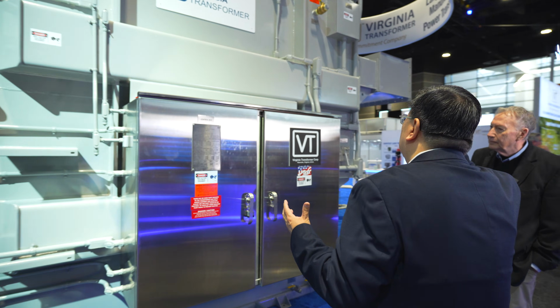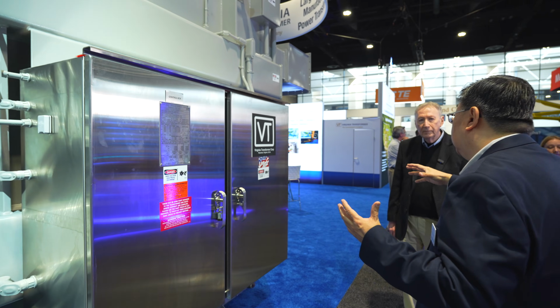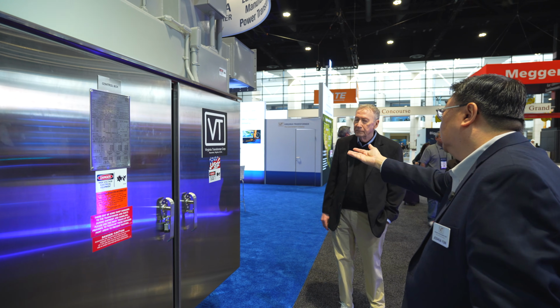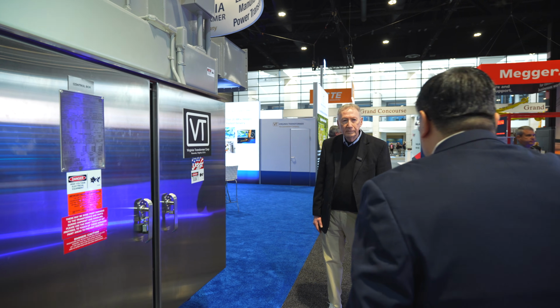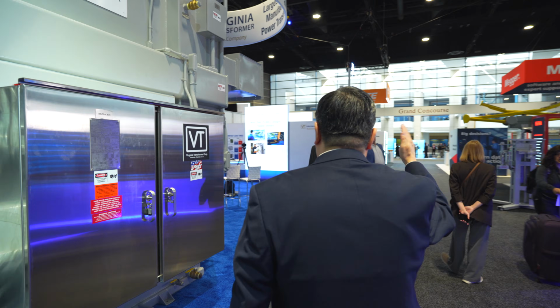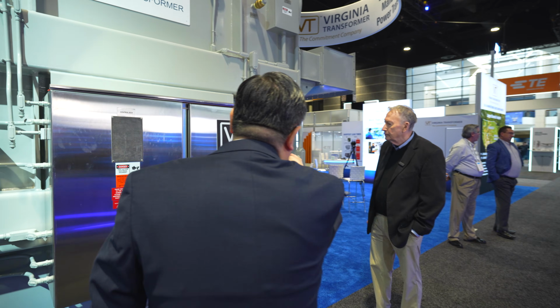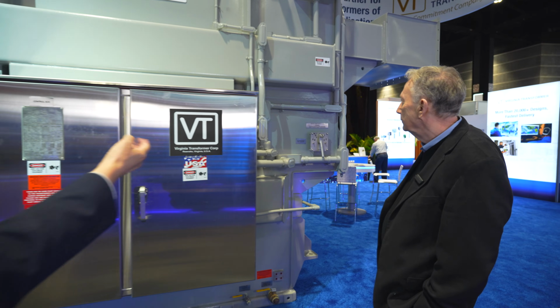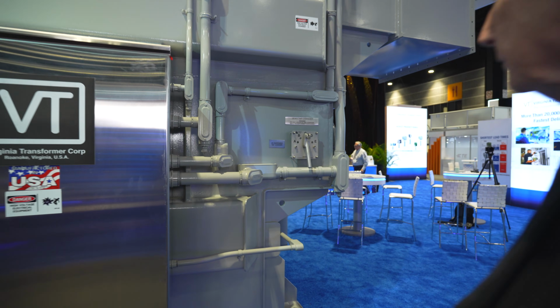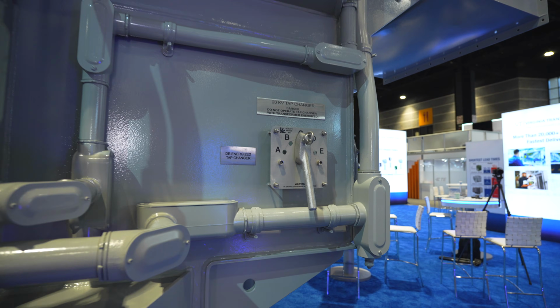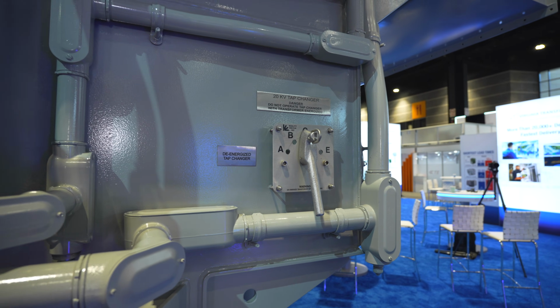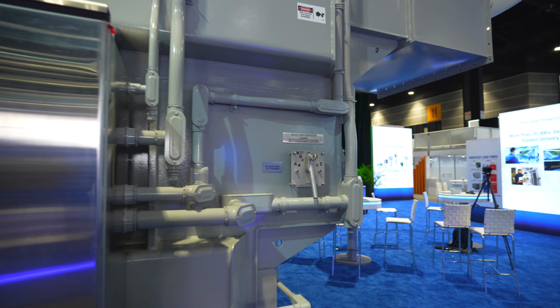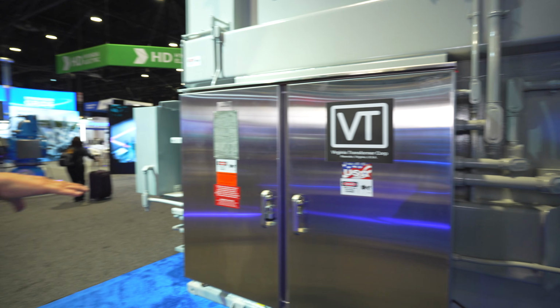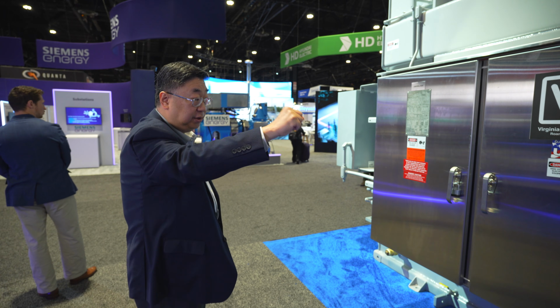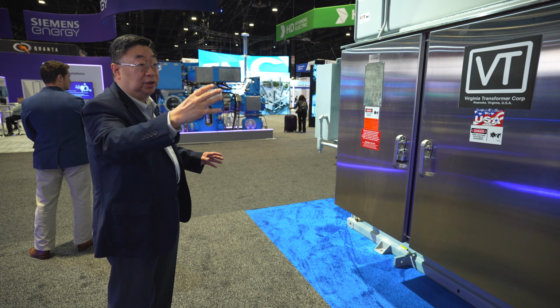On the primary side, the incoming voltage can actually be changed depending on the level—you can regulate the voltage using what they call a de-energized tap changer. This gives you a bit of variation if necessary; if all of a sudden there's a voltage dip, you don't want to cause a disruption, so you can de-energize this, change the tap, and make the physical adjustment.